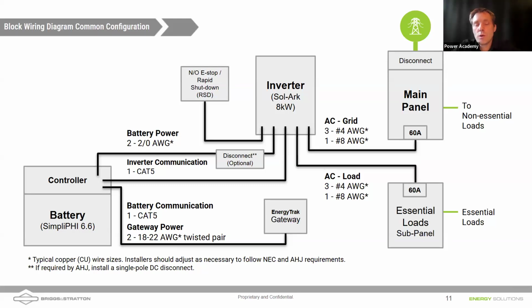Yeah, so excellent question. So the question, I believe, as you said, is, hey, if we're using this off grid, do we have the ability to pull 200 amps through the inverter? And I think the answer to that question, if I've phrased it correctly, is that as long as you connect the generator to the grid input, then you should be able to pull 200 amps of continuous power from your generator. Now, of course, you'll need a generator rated at 48 kilowatts to do that, right? But you do have the ability to pull that much power through the grid port. If you hook it up to the generator port, you're going to be limited to 80 amps of continuous power pulled from the generator and sent to loads. And if you're looking at the output of the inverter from battery only, you're limited to 12 kilowatts, which is 50 amps of continuous power. So hopefully that answers your question.